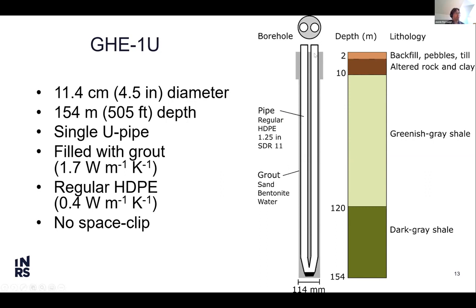So we installed this single U-pipe grouted borehole. The thermal conductivity of the grout is 1.7 watts per meter Kelvin, which is typical for a bentonite-sand mix, with regular HDPE pipe. There was no spacer clip. Sometimes we put in a spacer clip to spread the pipes apart to decrease thermal short-circuiting. In this case, no spacer clip was installed.